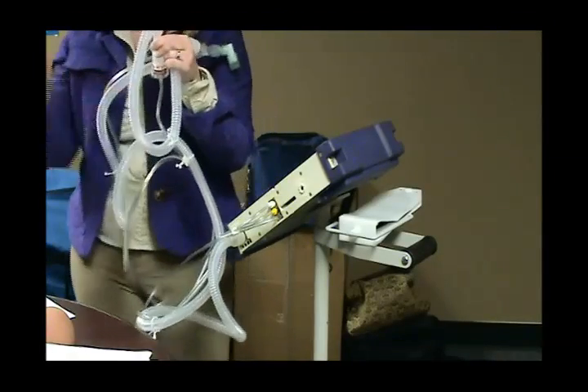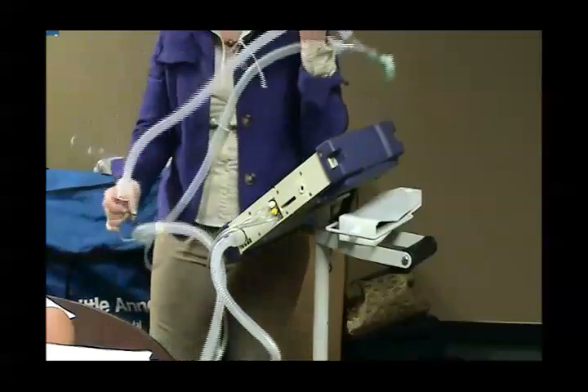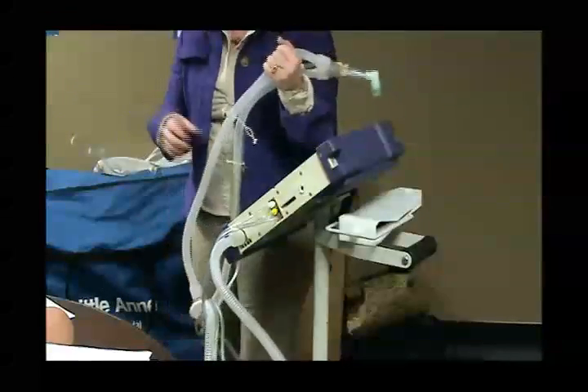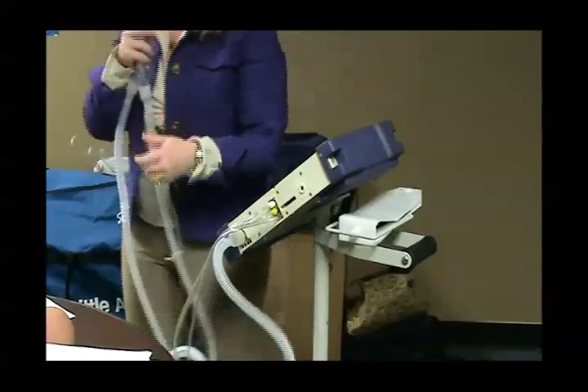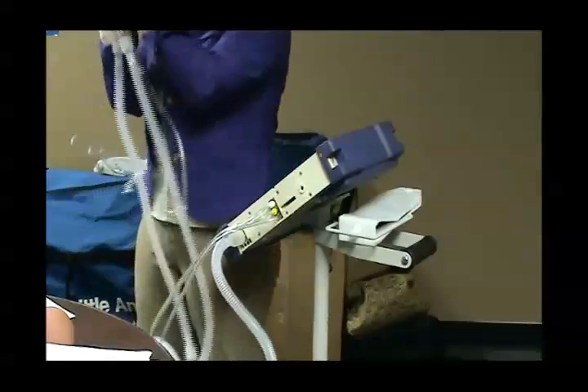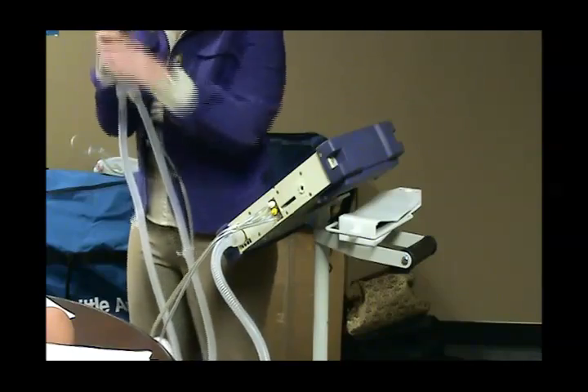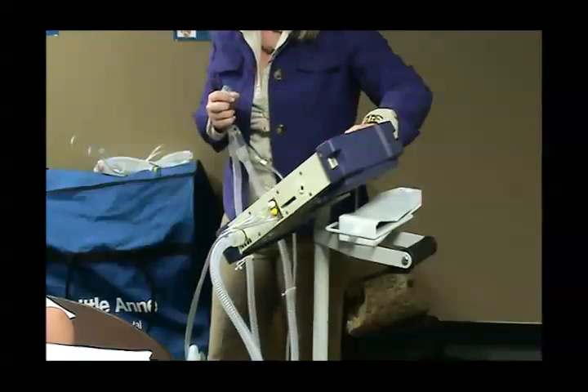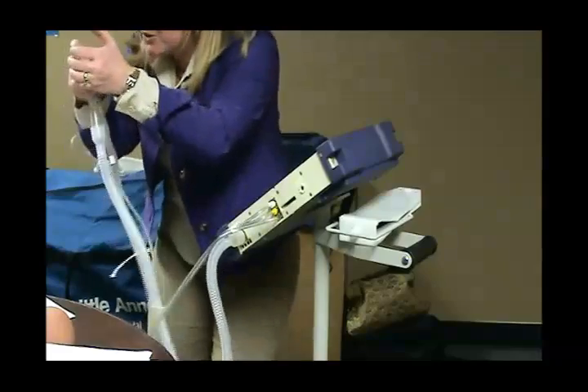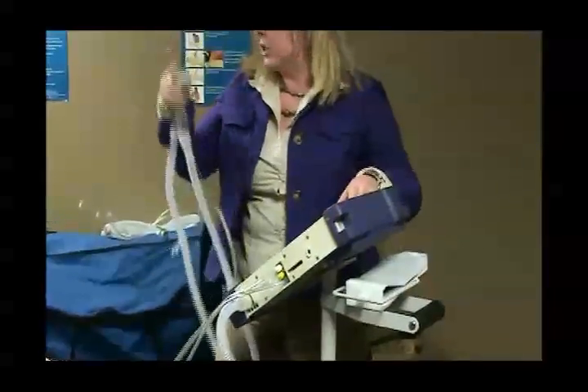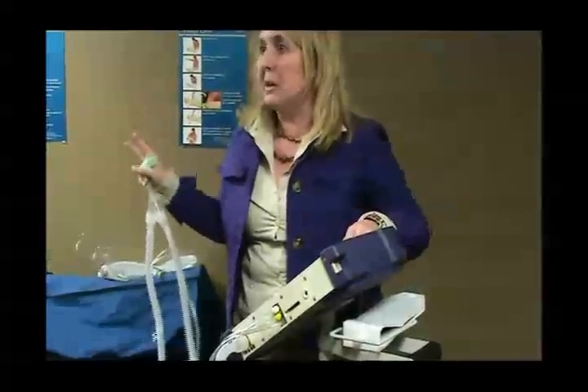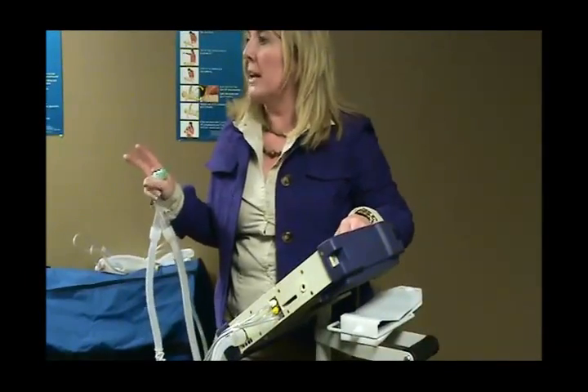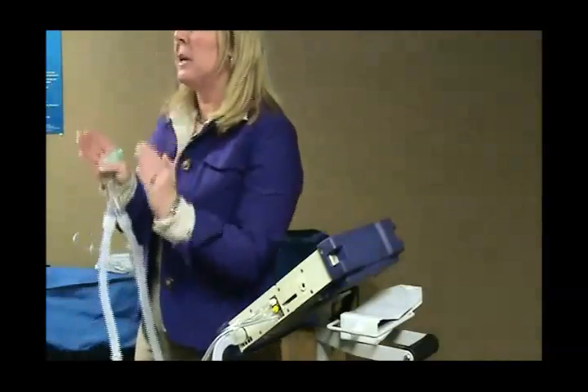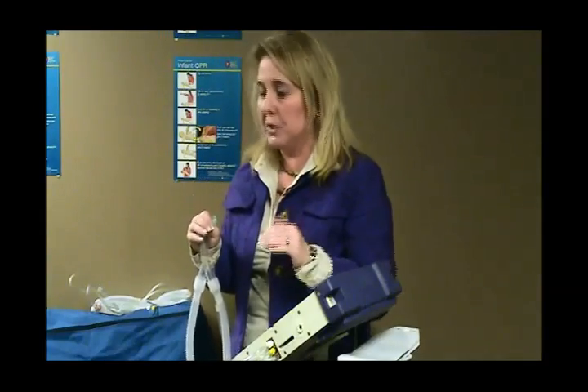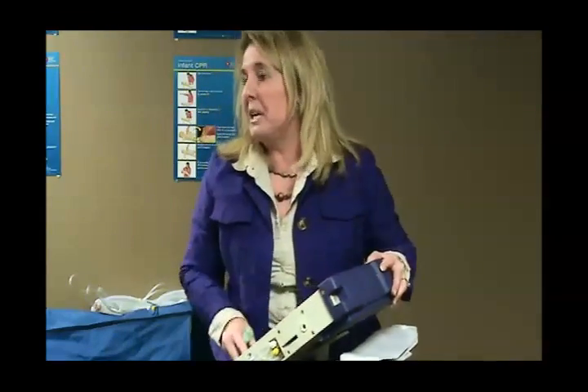So when you're setting up a new circuit on that ventilator, the first thing that you do after you get it on there, if you're switching it out while it's on the patient, go ahead and put it on the patient, eyeball it to whatever PEEP it's supposed to be, and then read it off of the ventilator, plus or minus 1. Don't stand there and do this until you try to get it exactly, because if there's somebody breathing on it, it's going to be dynamic. You'll be there all day. Okay? Plus or minus 1. If the patient is very PEEP dependent, and a fluctuation of a PEEP of 1 is going to be clinically detrimental to them, they will be on your ventilator with the internal PEEP.